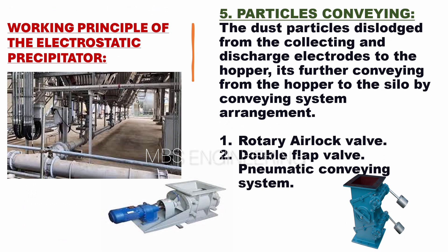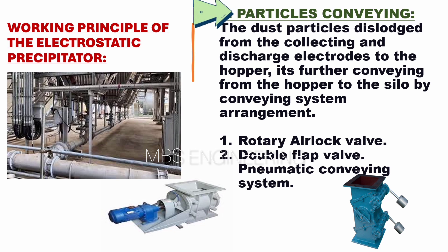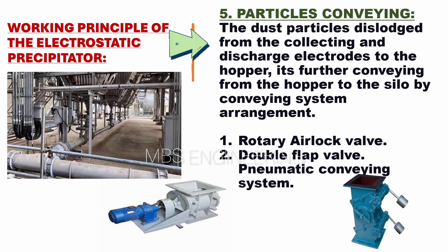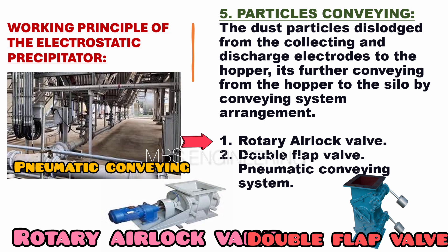The fifth step of the electrostatic precipitator's working principle is particle conveying. The dust particles are dislodged from the collecting and discharge electrodes to the hopper, and further conveyed from the hopper to the silo by the conveying system. The dust disposal arrangements used include: the rotary air lock valve, the double flap valve, and the pneumatic conveying system.